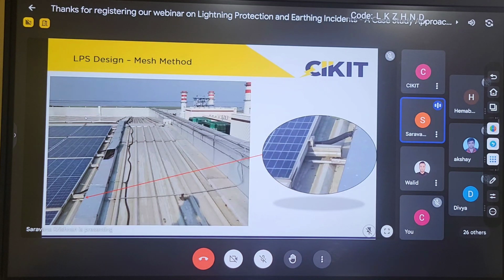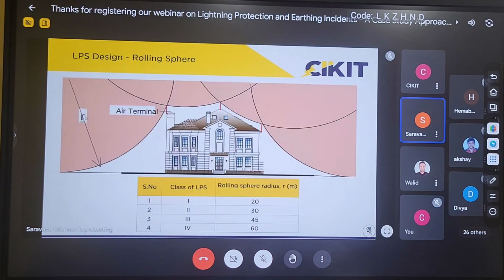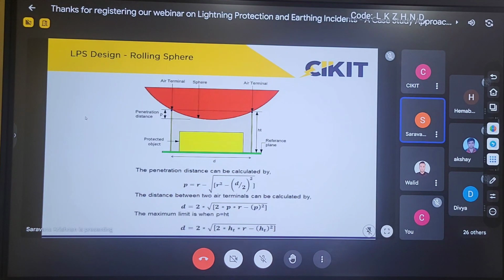The commonly used method is the rolling sphere method. Here we roll an imaginary sphere over the structure to be protected, and we need to ensure that the sphere does not make contact with any part of the building. Here also, the radius of the sphere depends upon the level of protection. For level 4, it will be 60 meters. We have explained in detail all the calculations, like the protection angle method and the rolling sphere method, in a separate webinar video. You can go through that video for detailed calculations. Here I'm just providing an outline.